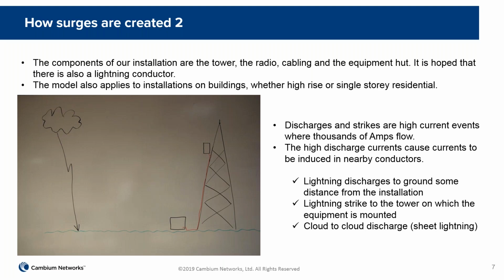In our lightning surge, we would have thousands of amps flowing, and just a small amount of that current is induced into the drop cable. Those lightning discharges could come from a strike to ground some distance away, kilometers away from the installation. They could come from a strike to the tower, the obvious one, where the tower itself gets hit. And they could come from cloud to cloud discharge. There's no cloud to ground discharge necessarily. It's just between clouds, sheet lightning, as we sometimes call it. All of those can induce a voltage, a current into our cabling.